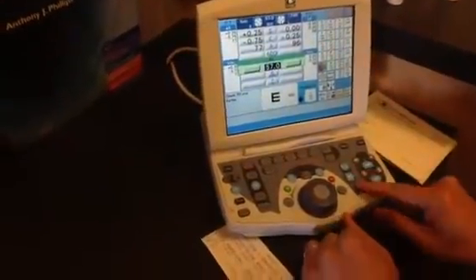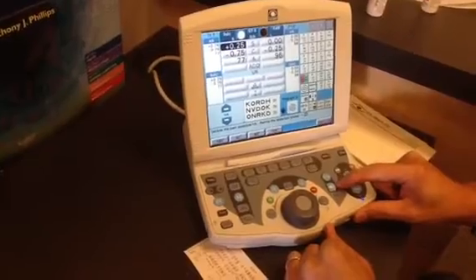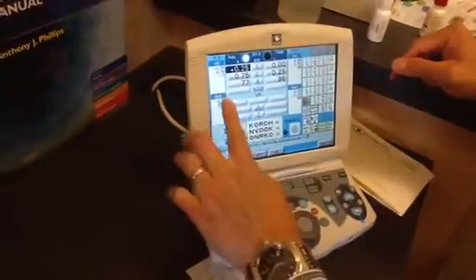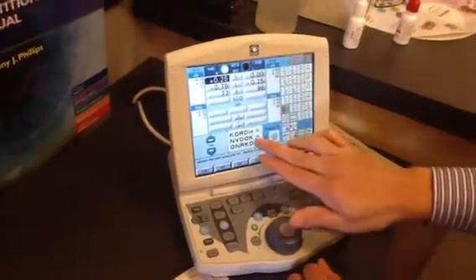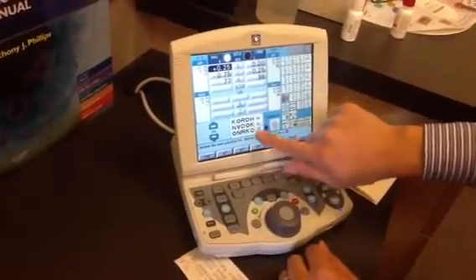Once they're lined up, press the same button again and it'll go to the next step. With this step, it covers one eye and starts on one eye so you can start your refraction. You can leave the whole chart here, which is what the patient is seeing — everything they see, you can see right here.